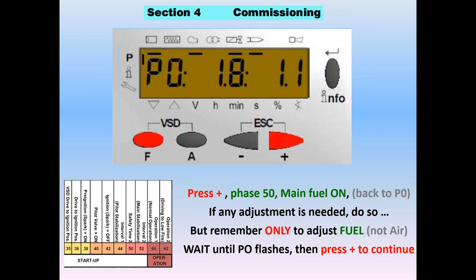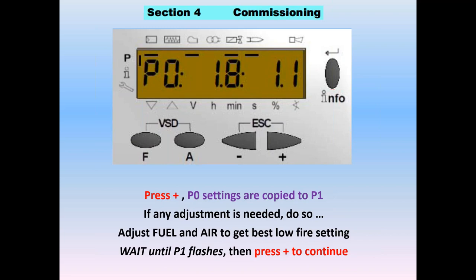Press plus to continue. We have P0 with values of 1.8 gas and 1.1 air — what we ended up with. Press plus, and it will automatically copy those settings to P1. P1 was empty before, and it brings over those exact same ignition settings as a courtesy. On P1, we have the ability to make adjustments to air or fuel at low fire. Ignition may have been very rich or very lean — adjust to whatever gives a repeatable light-off every time. We're not overly concerned with exact combustion on ignition; we just want a strong, steady, repeatable light-off.